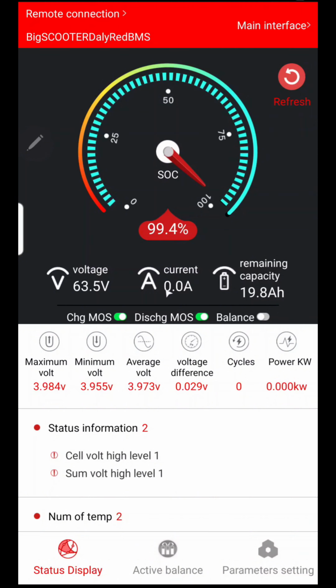We're not showing any current drain because we're not using it, just capacity remaining. Then down below it gives you the maximum voltage of a cell string, one of the 16 cell strings, the minimum voltage, average voltage, voltage difference, and it will tell you the number of cycles and power drained if we were using the battery, which we're not at the moment.